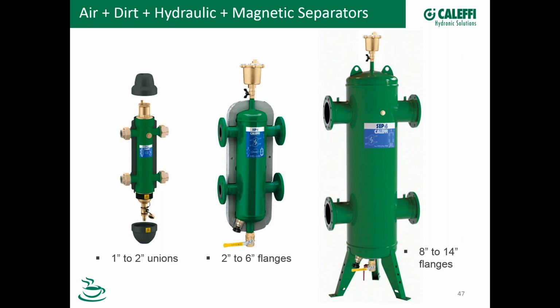And you can see a picture here. This one shows the magnet is the insertion type. So this has the dry well that goes up in the return flow path, in this part of the device where we're scrubbing out the dirt. And that has a commercial size air vent on the top of it as well. And then these great big ones, on up to 14 inches, they have legs. This picture actually shows one magnet, but there are actually 3. These really large ones have 3 insertion magnets on the bottom. And again, here's a location for a sensor and our commercial size air vent up on top. So that sums up step 4.